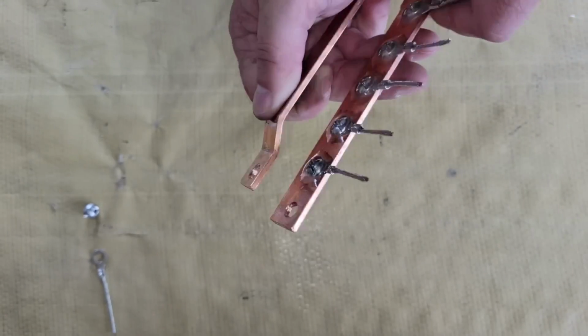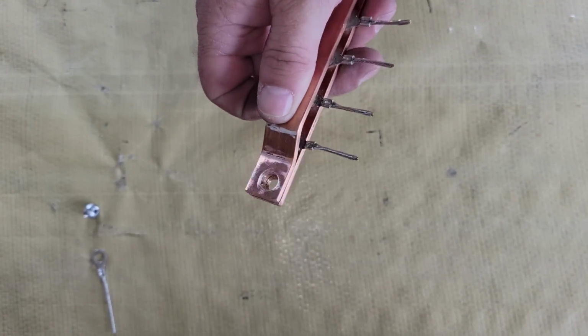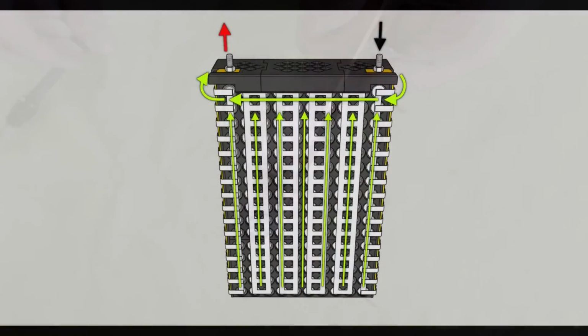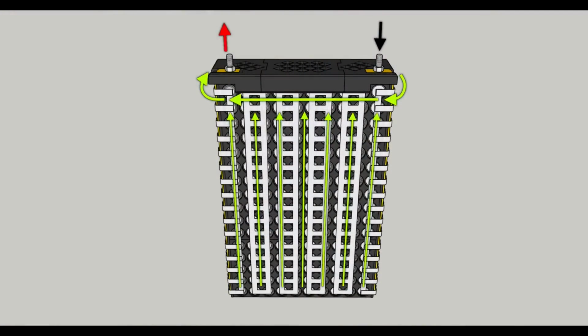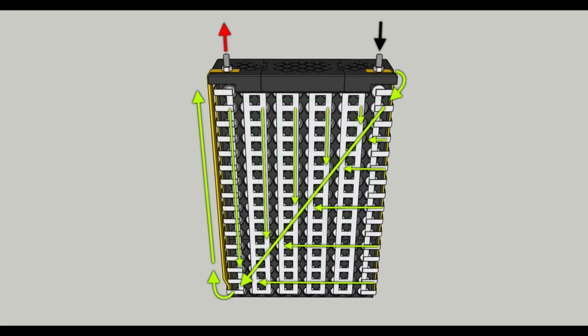If the bus bars on each side were identical, then the current being pulled through the battery would choose the path of least resistance, which means it would flow directly through the cells in the top of the battery only, and the rest of the cells would trickle charge the top cells to equalize afterward, as shown in the picture. This would lead to the top cells being worked harder and degrading a lot faster than the rest, if it doesn't damage them completely from the start.